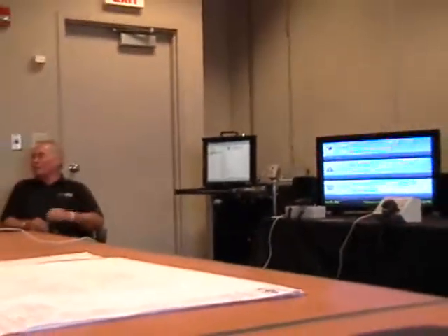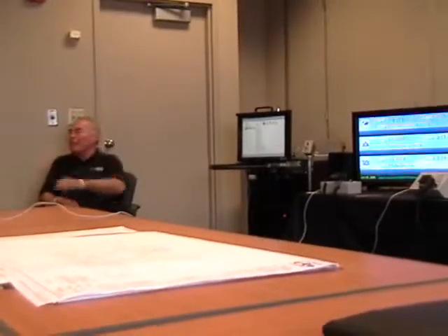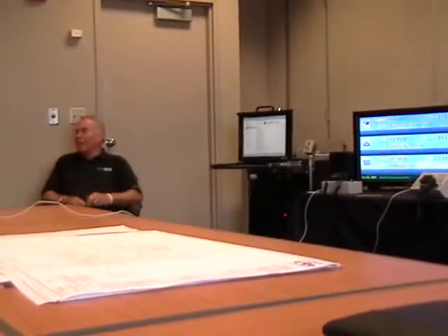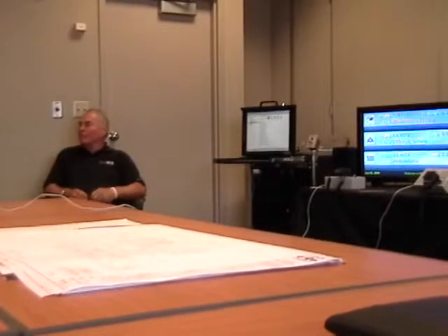And they have that capability now to do the back, they just don't have all the monitoring with the new hardware. But don't have all the monitoring and everything to show that. Right. The other thing that we have now, well, if you had an all-digital system, you have 3 ACSs here. If it was all digital, you could have a 4th ACS that's just sitting out here online, and if any one of those went down, it would automatically switch the backup in. What it does, the backup actually assumes the IP address and all of the one that failed.